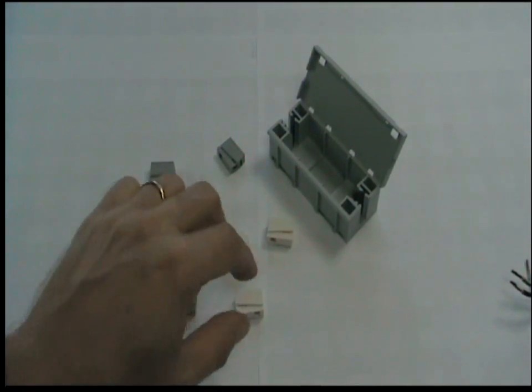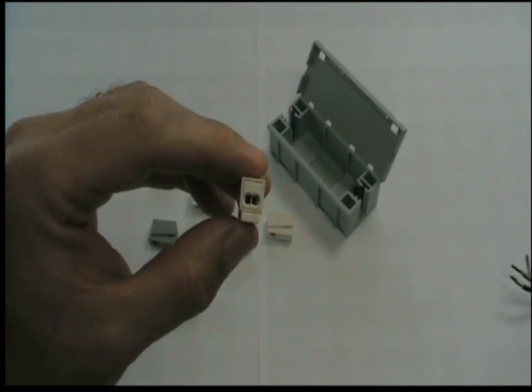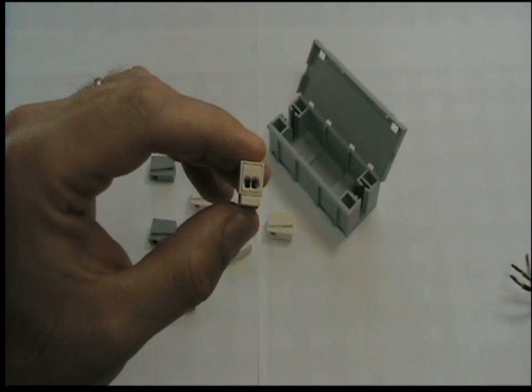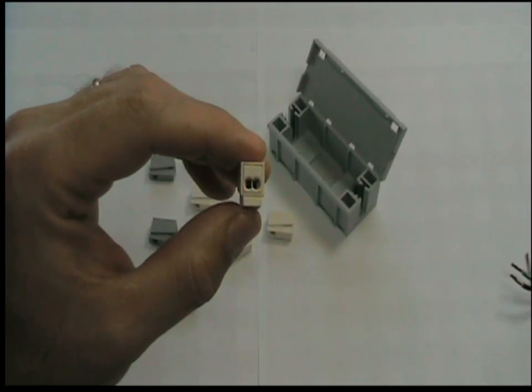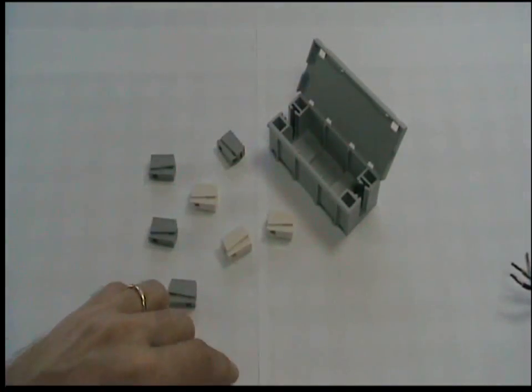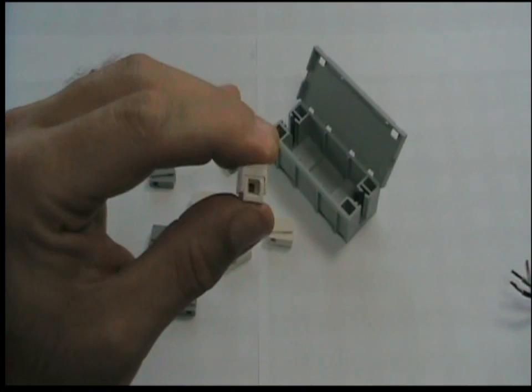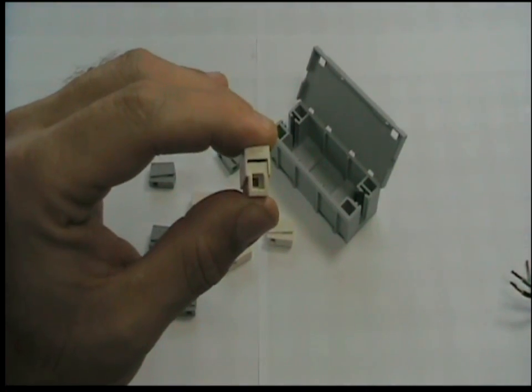The 224112 terminal is a 2 to 1 connector which can connect 2, 1, 1.5 or 2.5mm solid cables on the push fit side and 0.5 to 2.5mm flex or solid core on the clamp side.